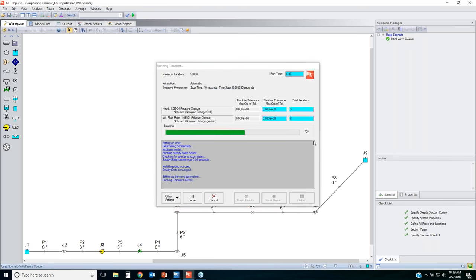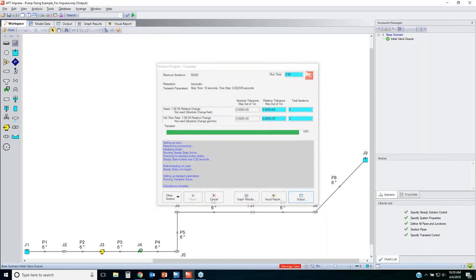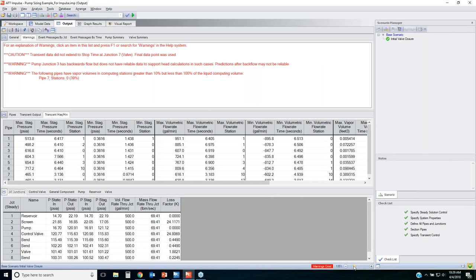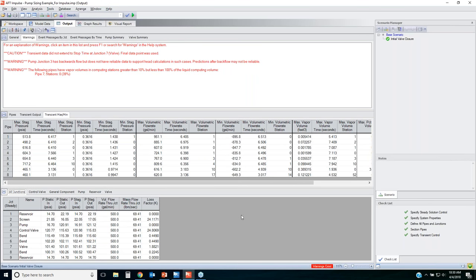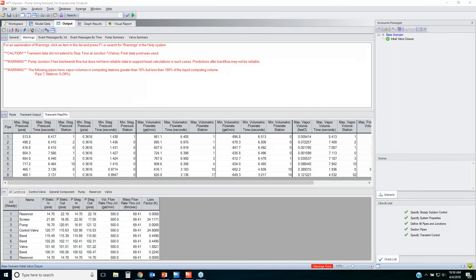Impulse is using the method of characteristics to solve the mass-momentum transient balances over time, having broken all the pipes into that grid and sections to figure out how flow rates, velocities, and pressures are changing throughout the system. Looking at the results and warnings: the first thing to figure out is the maximum system pressure. Looking at the transient maximum table, the maximum pressure is 717 PSIA right at the valve inlet — that's a really high surge pressure.